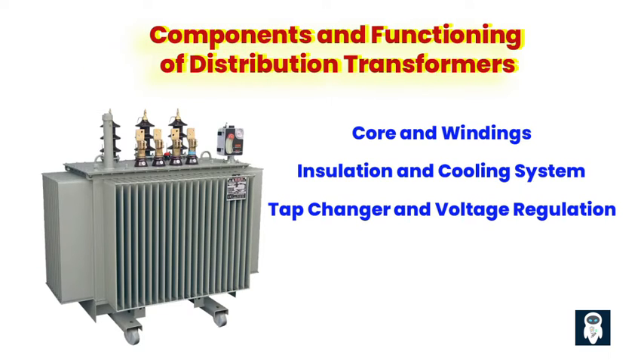A transformer is a complex electrical device that consists of several essential components working together to facilitate the transformation of voltage levels. The primary components include the core and windings. Just like a human body has a skeletal system, distribution transformers have a core and windings that make up their internal structure. The core is typically made of laminations of electrical grade steel, providing a path for the magnetic flux generated by the transformer. The windings consist of copper or aluminum conductors coiled around the core, which help in the transformation of voltage.